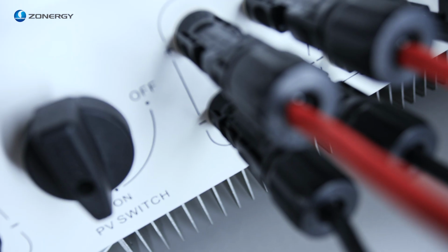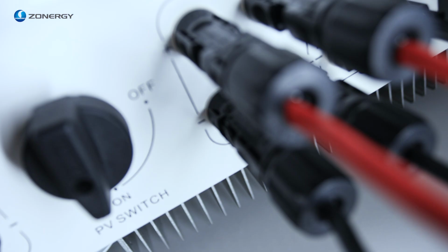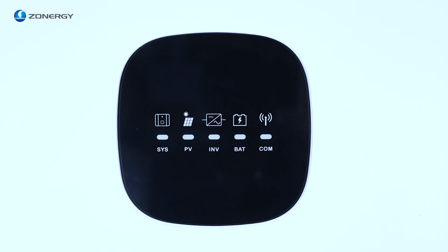Step 4. Turn on the DC switch of the inverter. Close the DC switch between the inverter and PV. Observe whether the 5 indicators of the inverter are all on. All on indicates that the inverter runs normally.